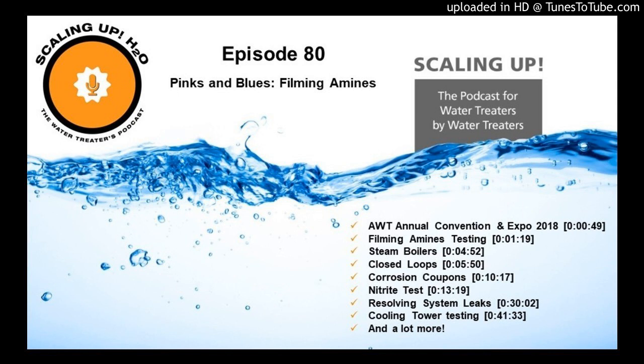So here's how I say to use the Filming Amine test, which, whichever one you use, works well if you use it like this: use it as a go, no-go test. If you have a positive for a Filming Amine, what that means is that the Filming Amine has coated the entire metal surfaces in the entire system, and now you have a residual left over. That's what we're going for. You need a residual.